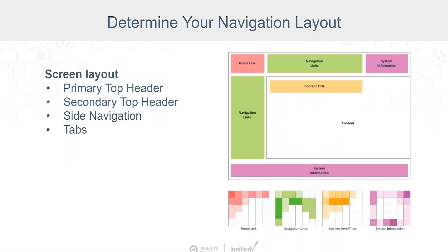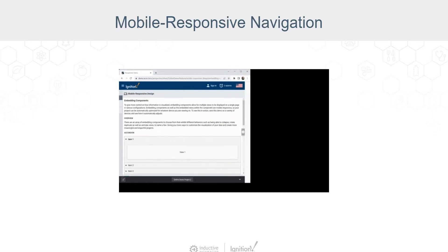Here we see some examples of navigation layout. The screen is broken up into top and side navigation, the main content takes up most of the real estate, and there are additional metrics along the bottom. Top navigation is typical because users intuitively look to the top of the screen. You might also have a home page link in the upper left, system information such as critical alarms towards the right, and optionally a second row of navigation buttons or side navigation. If you start planning with responsiveness in mind, you'll save time later — this shows a self-hiding navigation drawer from our online demo, where the menu is replaced with a hamburger icon when the screen size is reduced.